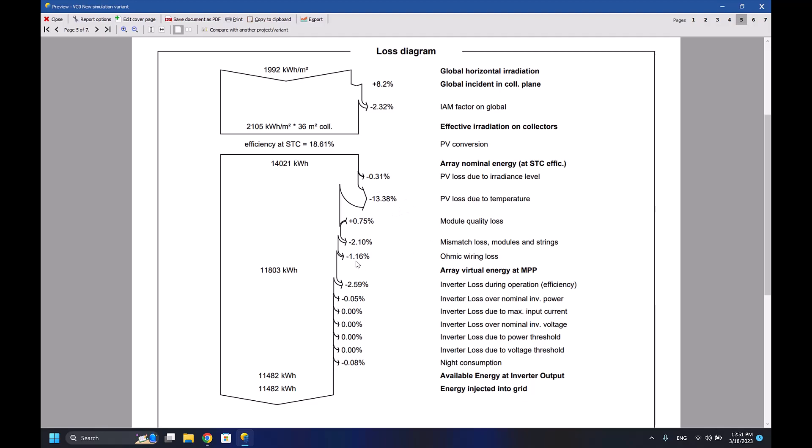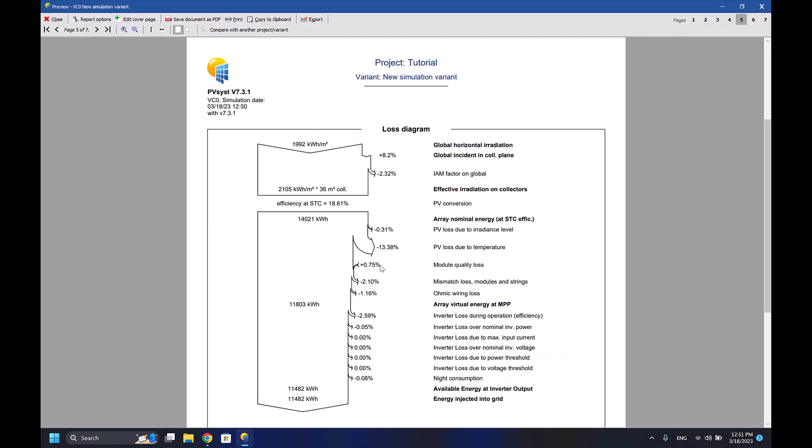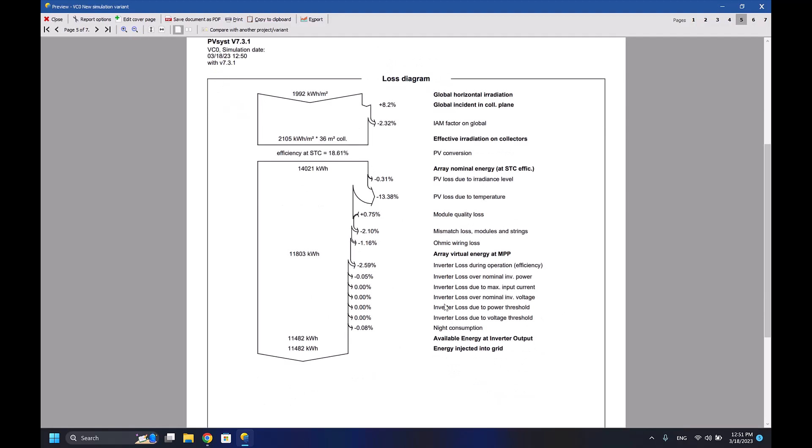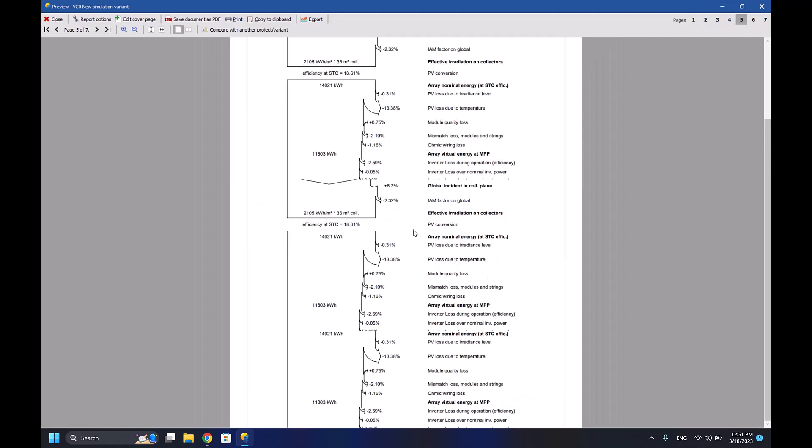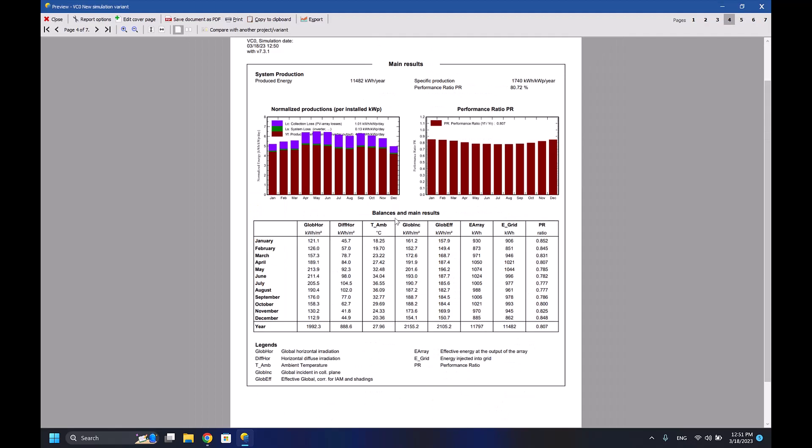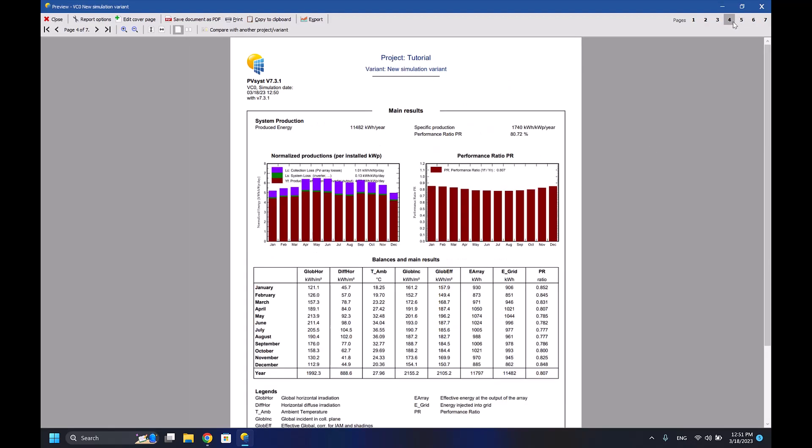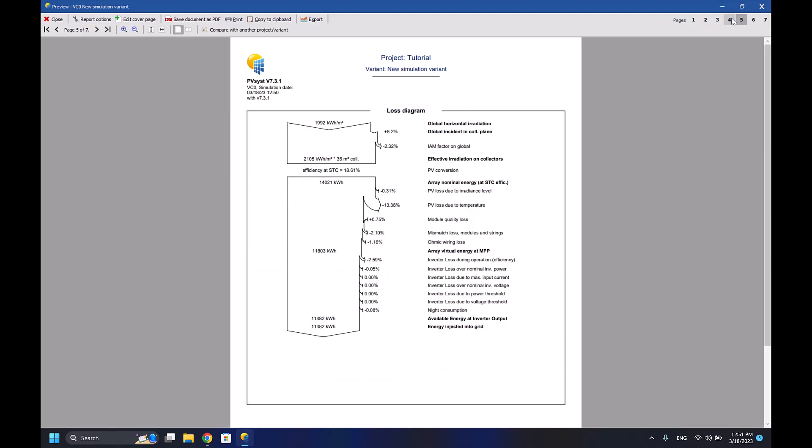We have ohmic and wiring losses 1.16%, the mismatch loss 2.1%, inverter loss during operation efficiency 2.59%. So as we can see here, everything is mentioned - how much power we have, how much losses, etc. These two pages are the most two important pages that you have to take care of.